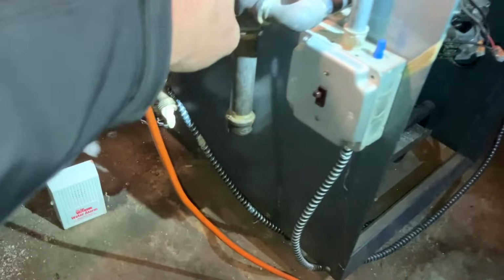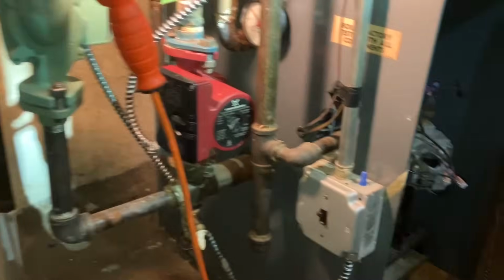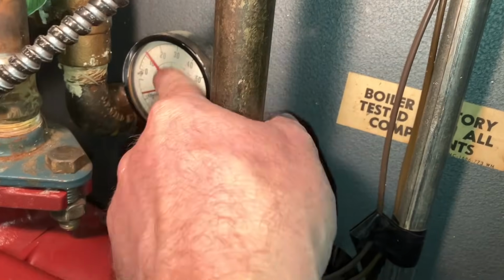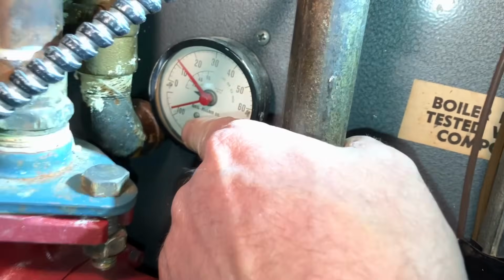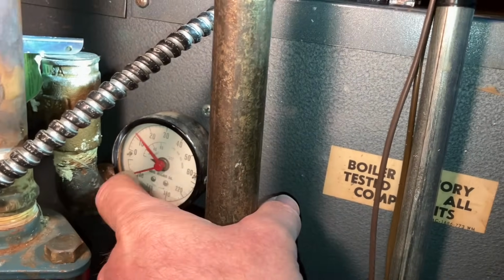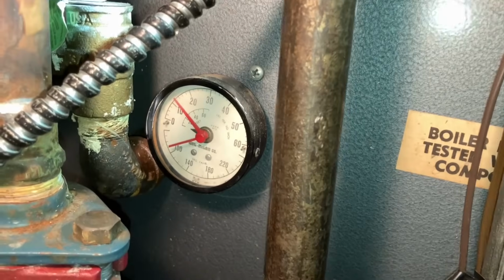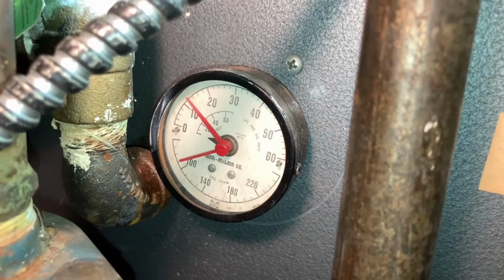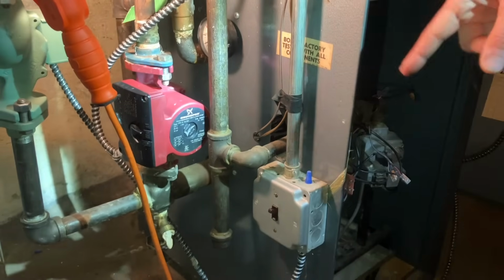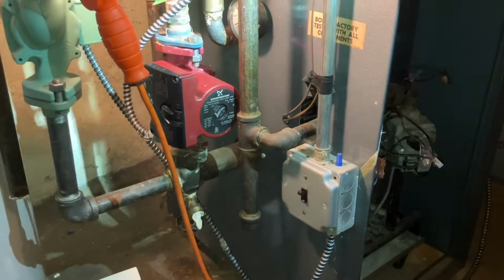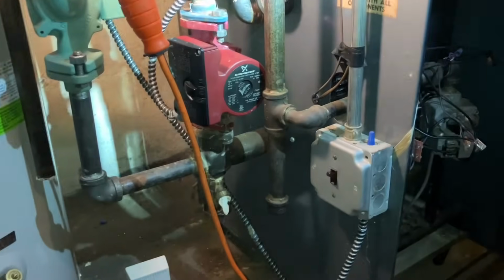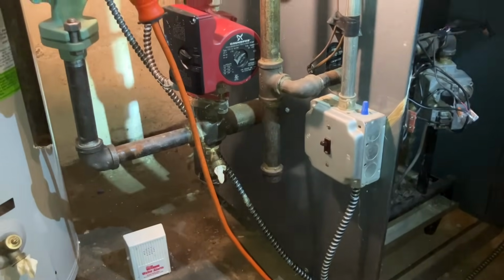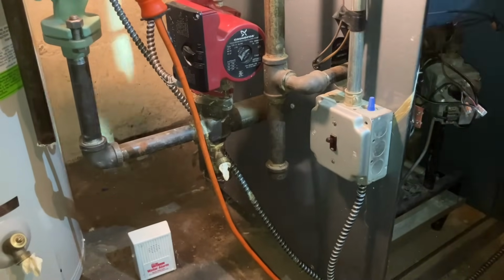Boiler drain. You have the circulator for zone 1, circulator for zone 2. Tridicator. Actually, it's a tridicator gauge. No, it's not a tridicator gauge. It only has 2 dials. One is pressure, one is temperature. That's an old... Can you verify something for me? Yes. I always make sure when I do the drain when I start the season, I bring it back up to 12, and then it heats up. Of course, the pressure goes up. But I start at 12 because it actually tends to dip below 10.